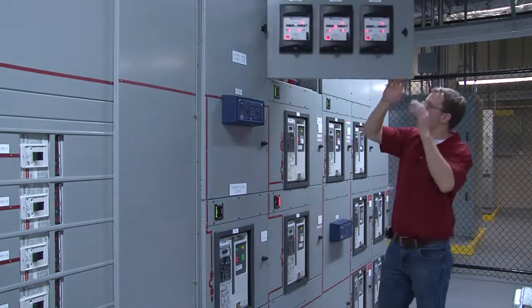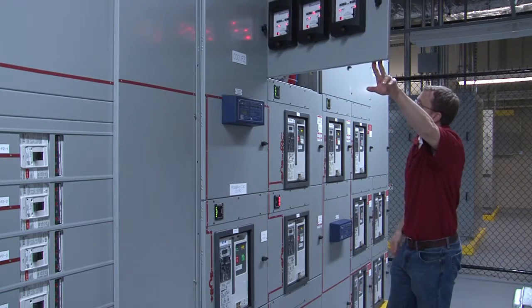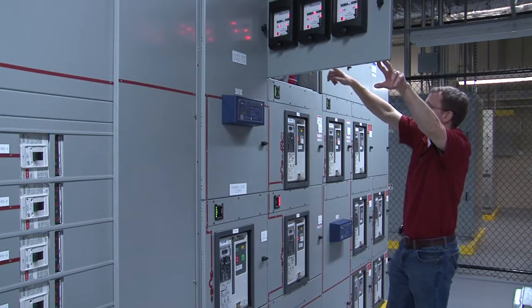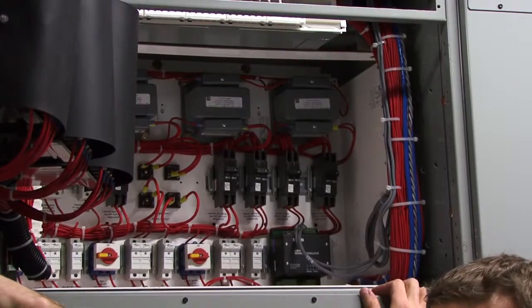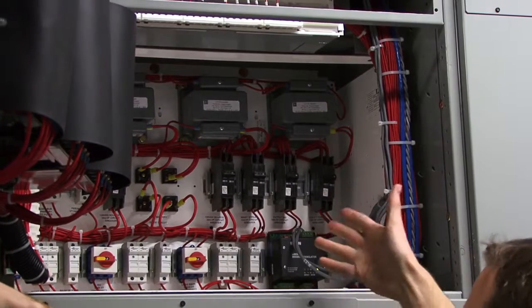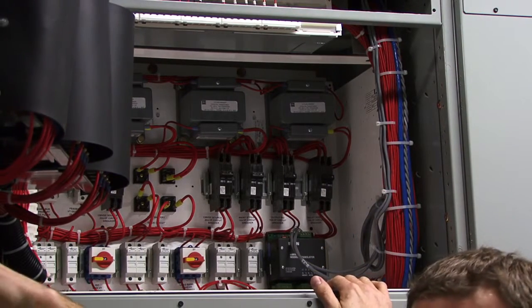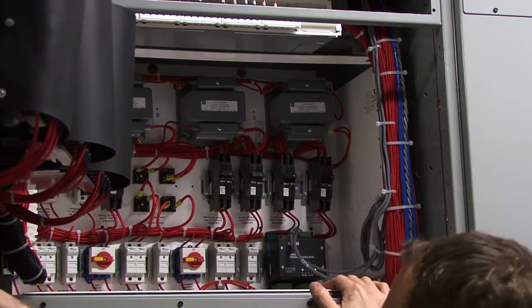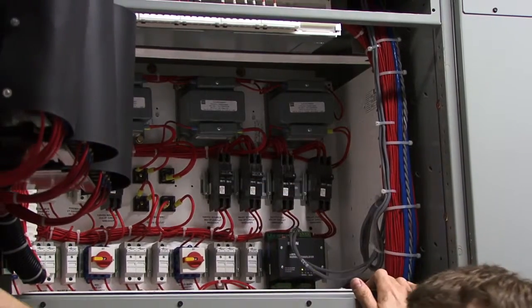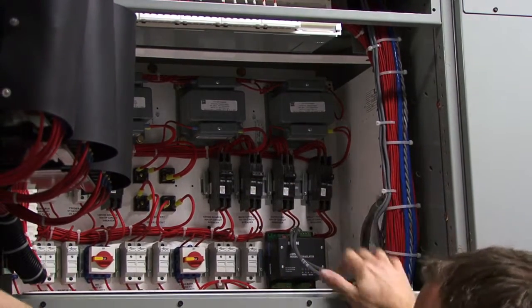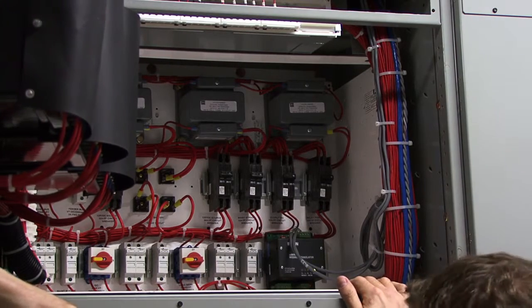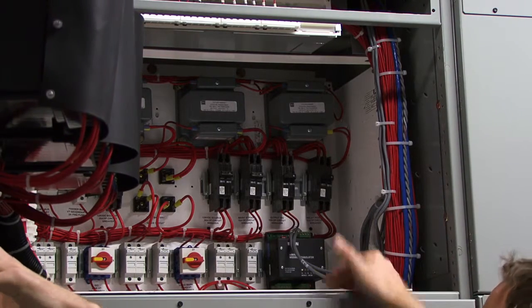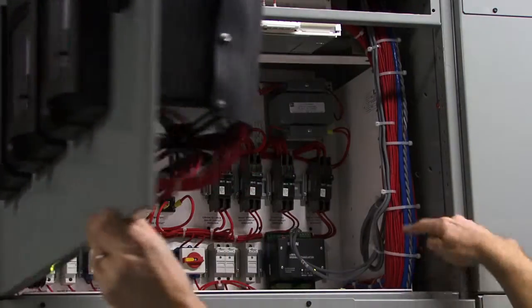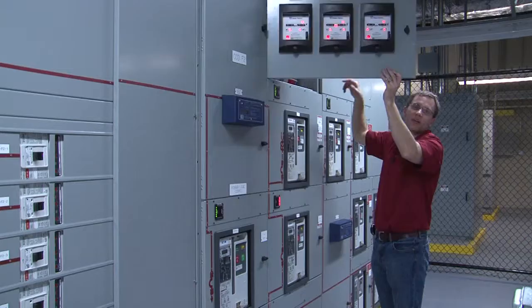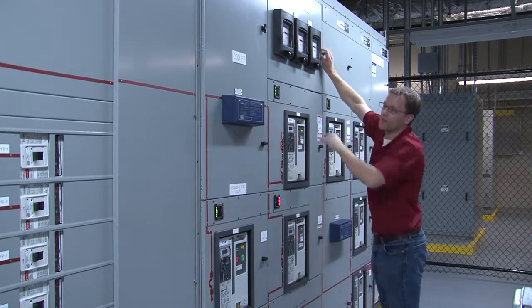You open this cabinet up. Across the top there are PTs. That's for your sync check relay sensing. You've got more black breakers that are for the DC distribution, which powers all the trip units of all the breakers. And then you've got a battery set of diodes in there, and then you've got switches to disconnect the PTs. Up there, your field interconnect wiring. There's the communication module. It communicates all the breakers back to Convergent.